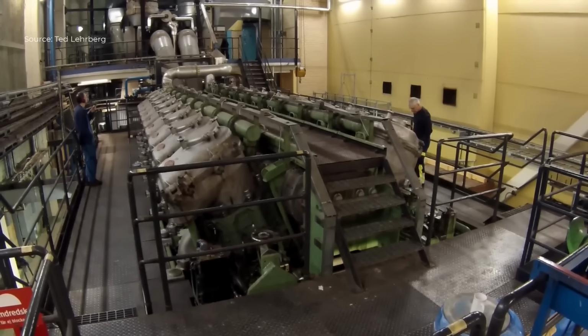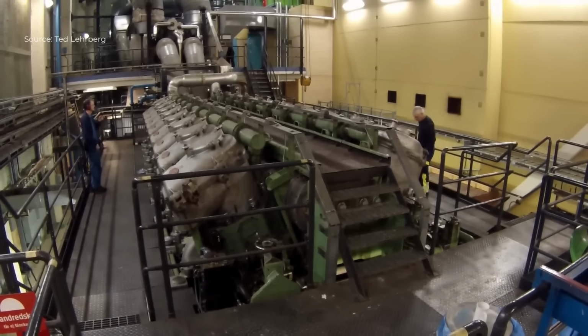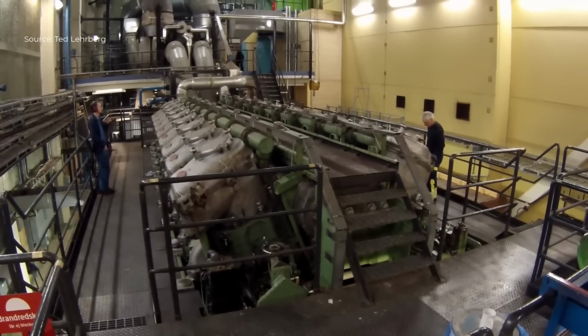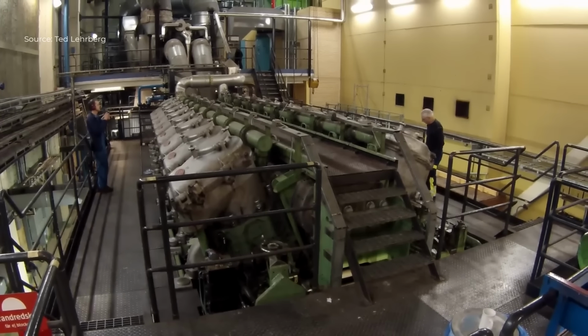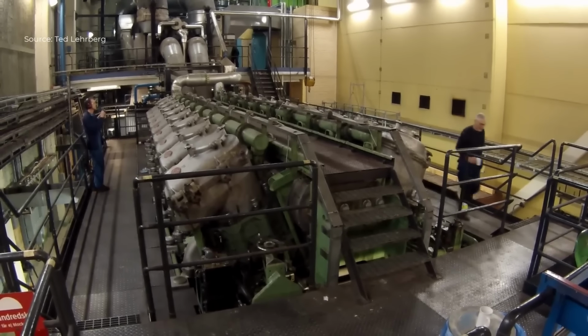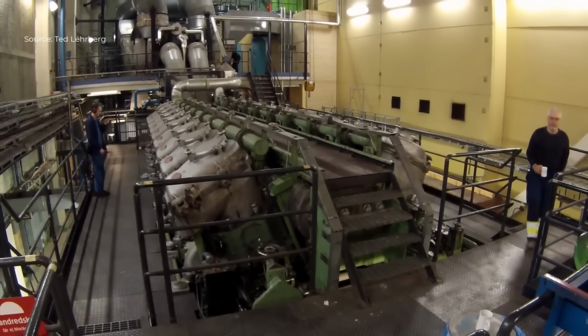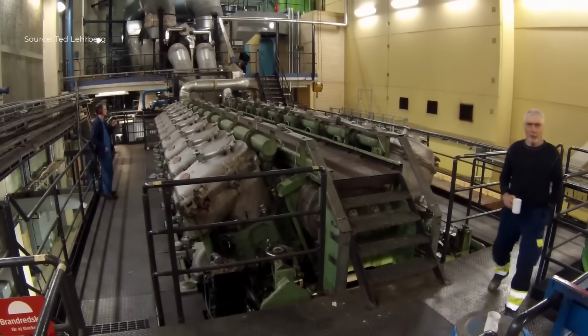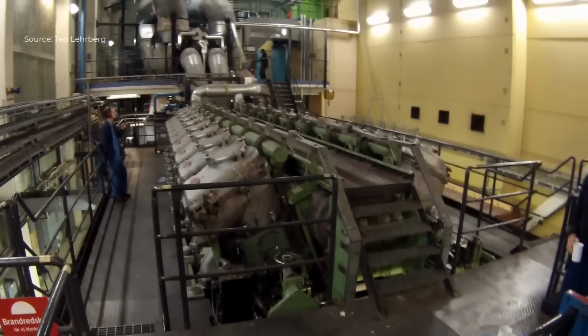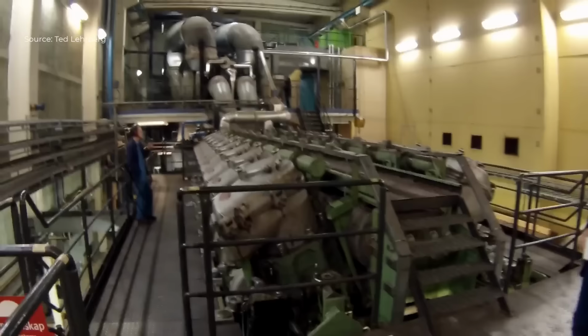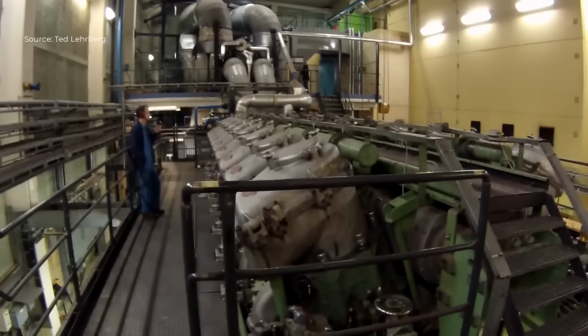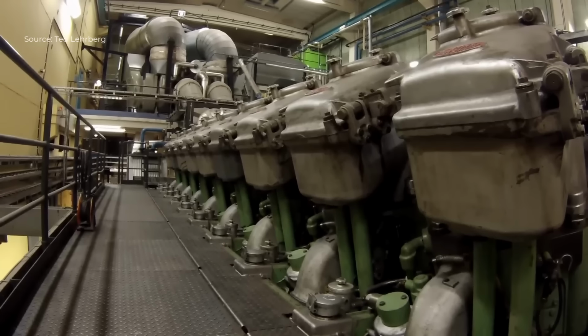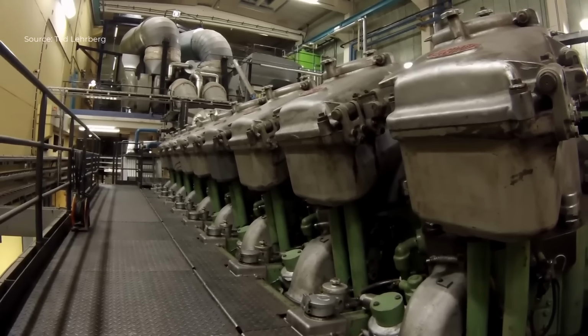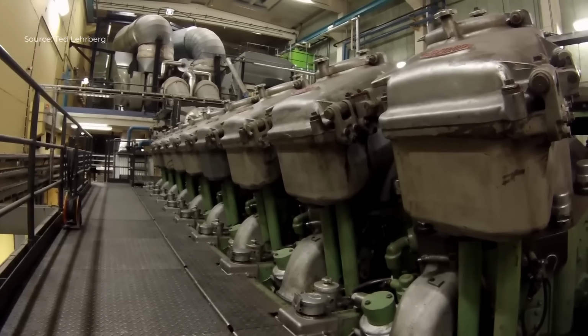The test procedure begins with a controlled warm-up phase. Initially, the engine is operated at approximately 25% of its rated load. This first heating stage allows all major components such as the crankshaft, pistons, cylinder liners, and bearings to gradually reach stable operating temperatures. Lubrication systems, cooling circuits, and fuel injection equipment are closely monitored to ensure proper flow, pressure, and response under light load conditions.